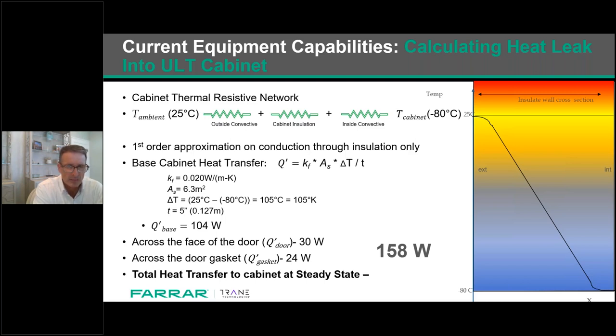So if you look at the bottom, when we look at the heat leak into a ULT freezer, we get to what we call the door gasket, and this is equivalent to 24 watts. However, this does not take into consideration a door gasket heater, nor a problem with a leaky door seal. That could be due to ice buildup. Those two phenomena could drastically increase the heat transfer to the cabinet from 158 watts to something much larger, causing the freezer refrigeration system to work much harder and longer than it was designed for. Next slide, please.